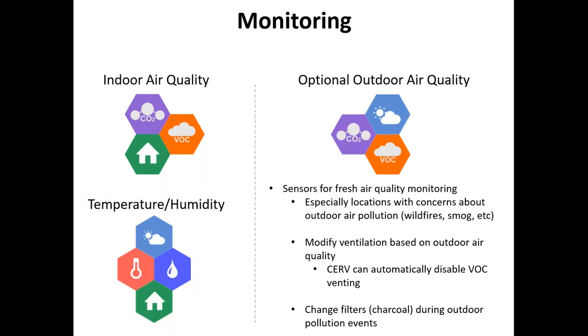The monitoring built into the system covers indoor air quality. It has independent CO2 and VOC sensors built in that sample from the indoor airstream. In addition, temperature and humidity are read on the inside as well as the outdoor. That is on the standard machine. And then something we'll look at later, a new feature is sampling the air quality on the incoming fresh air. That lets you modify ventilation based on the outdoor air quality as well, or make adjustments to operation or filters.